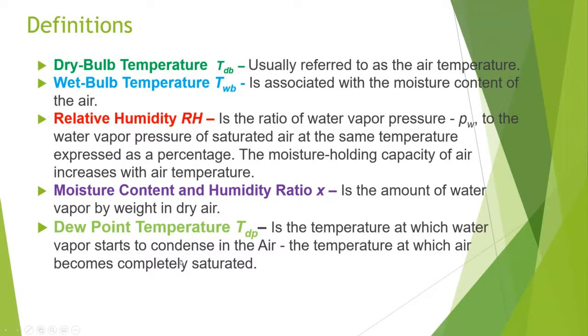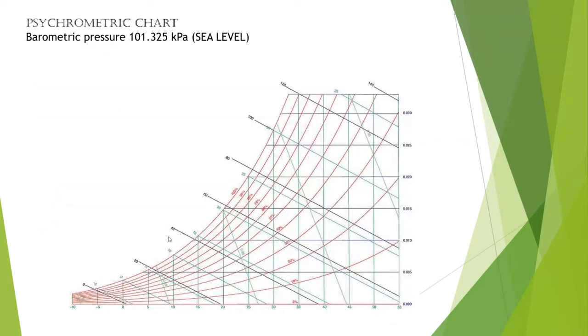Dew point is critically important for instrument mechanics because we do not want water condensing out of instrument air in a supply system that provides air to control valves. When that happens, valves stop working — and a valve failing in a bad position is a serious problem. The psychrometric chart is based on a specific pressure, generally one atmosphere or 101.325 kPa, and contains many different lines.